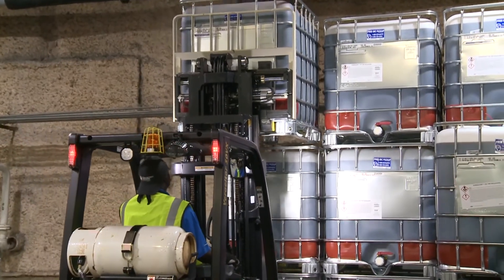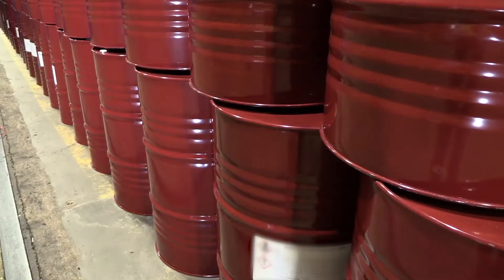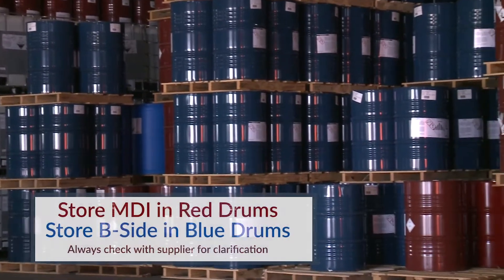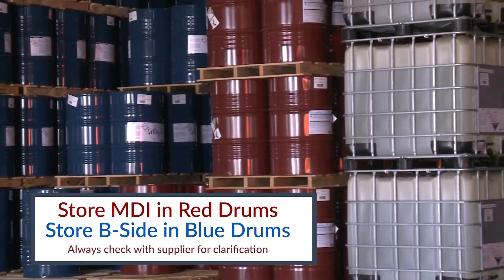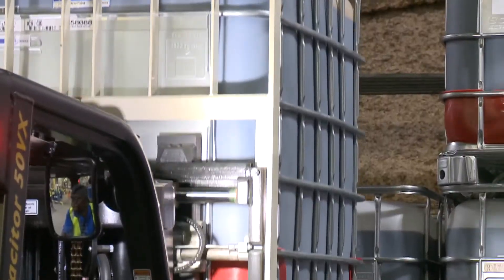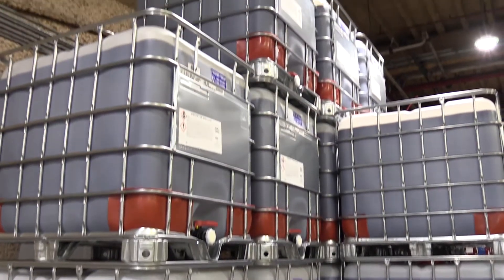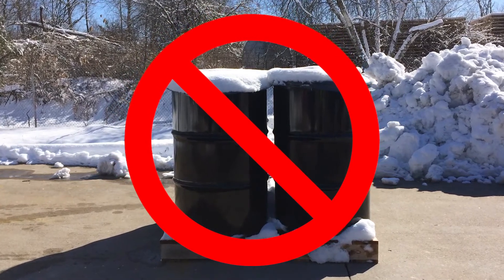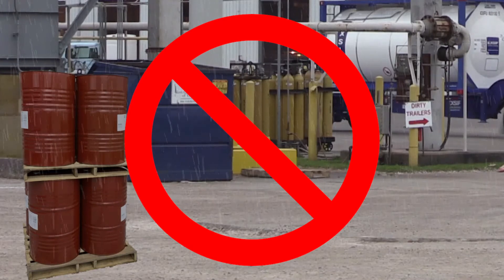Intermediate bulk containers can be made of either metal or a variety of other composite materials. For drum and intermediate bulk container storage, drums are commonly stored on their chimes or on pallets. Drums may be stacked — check with the supplier for additional guidance. Intermediate bulk containers can also be stacked with certain limitations, and manufacturers specify stacking limits on the IBC label. Drums and IBCs are stored in an area that protects the product from contamination due to moisture intrusion or degradation due to extreme temperature exposure.